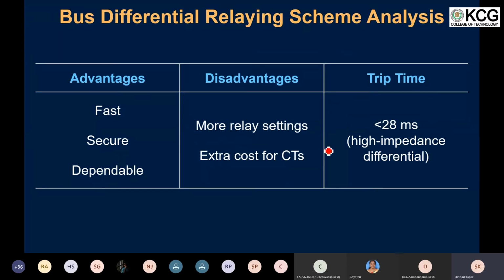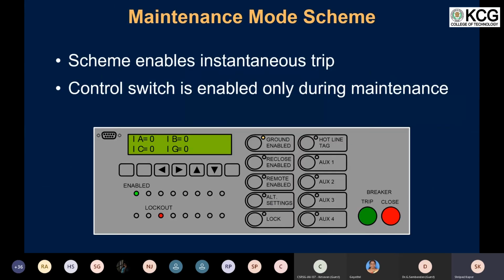And if you look from the operational point of view, the operation time is going to be less than or almost equal to about 30 millisecond. There is another method which is used, that is the maintenance mode. In the maintenance mode, basically what we do is you assign a high sensitive overcurrent element in the same relay. But this particular overcurrent element bypasses the time coordinated system. It basically takes off the time coordinated system, and only the operator, whenever he is going to work on a particular switchboard or a switchgear, is going to enable this mode.